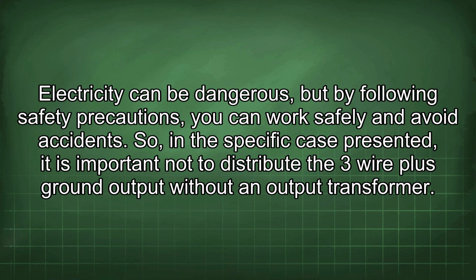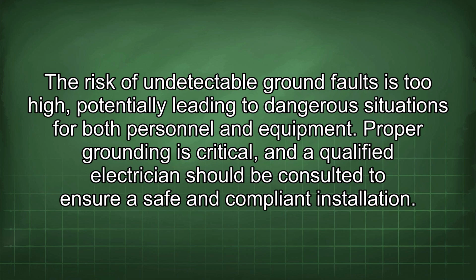So, in the specific case presented, it is important not to distribute the 3-wire plus ground output without an output transformer. The risk of undetectable ground faults is too high, potentially leading to dangerous situations for both personnel and equipment. Proper grounding is critical, and a qualified electrician should be consulted to ensure a safe and compliant installation.